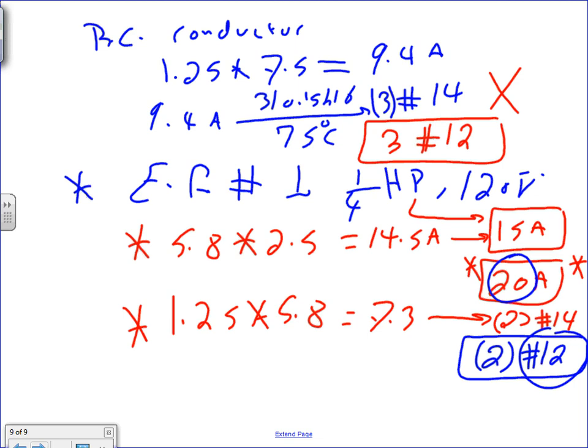But if you do the calculation, the first one is 15, and you're going to add, take this. If you do them in the tool, the overcurrent protection device is 15, add another 5.8 to it, you exceeded the rating of the overcurrent protection device. So you might have to put a 25 amp circuit breaker on them. Yes, you can, but you have to do the calculation. I personally would throw a dedicated circuit for them, 20 amp circuit, go feed them, pick them up.